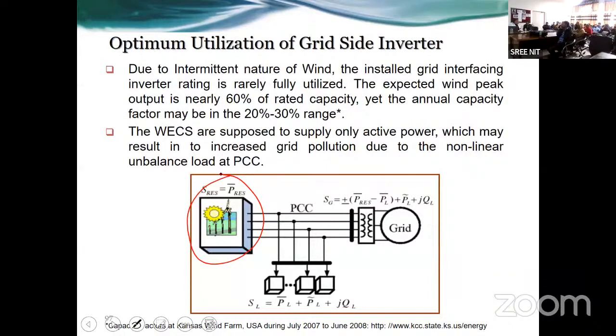That kind of study was going on, and at that time I suggested: why are we going to install a STATCOM? We can utilize the converter that is going to be used for evacuating power, the grid tied inverter. That inverter itself can meet the reactive power load demand, or harmonic compensation, or any kind of thing. That is the smart concept which I introduced in the system, and now it is a standard worldwide.